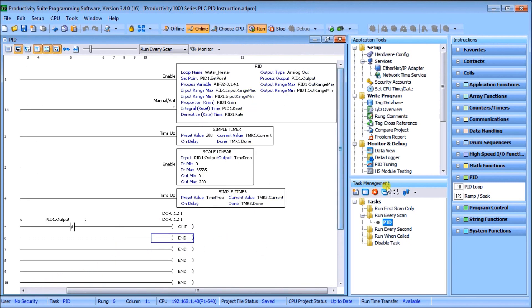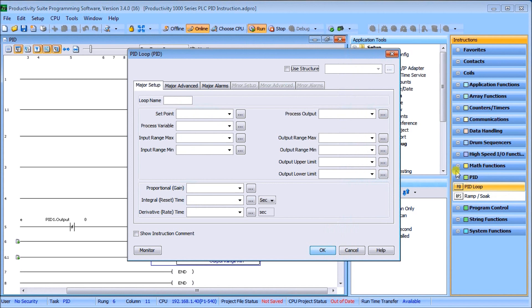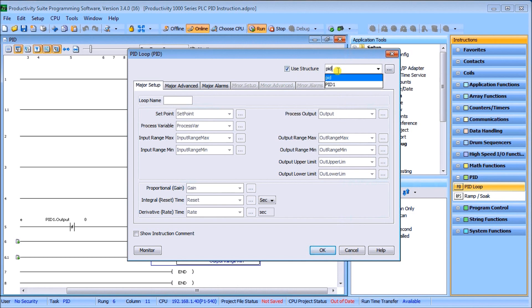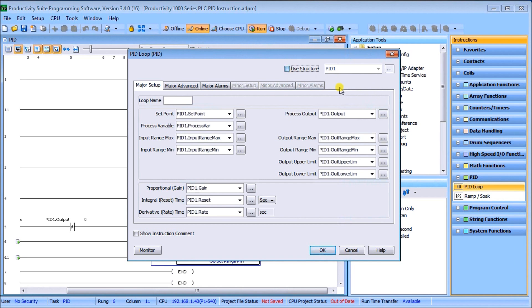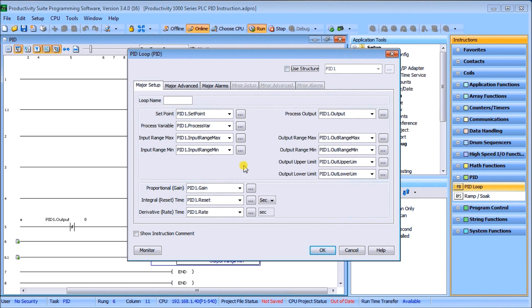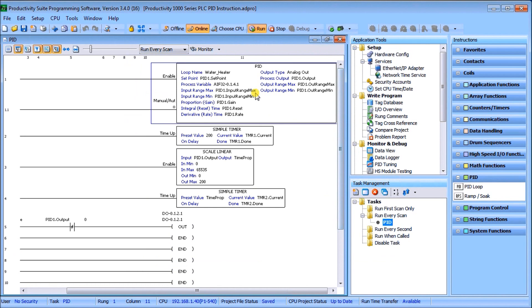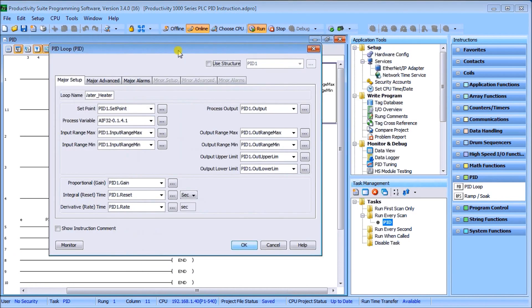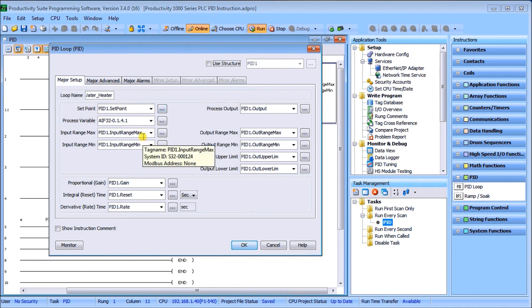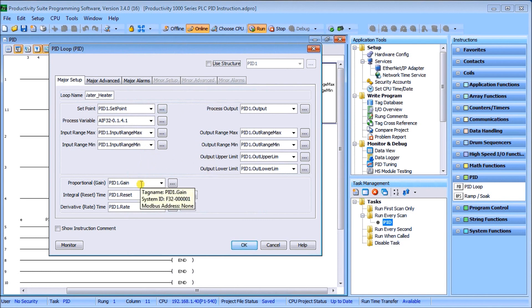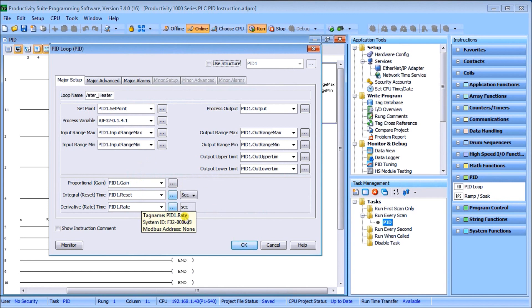The first thing we'll do is take a look at a PID instruction. Over on the left-hand side here, you'll see a PID loop under the PID instruction. When we double-click on that, the first thing we'll do is actually add a structure and we'll just call this PID_1. Once I name the structure, what this does is it will set up all my parameters so I don't have to set that up again. Then we have our process variable, which is our input to our PID instruction. My process variable that I have is actually my thermocouple input. Then I have my PID setpoint and my output, and then I have my input range max and mins, my output range max and mins, upper and lower limits, etc.